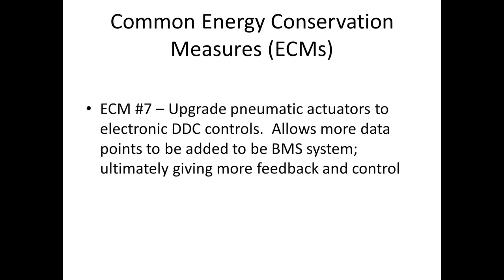A lot of times upgrading pneumatic actuators to electronic DDC controls. This isn't necessarily more inherent, just upgrading technology, but with a lot more electronic controls, we can be a lot more precise and have precise measurements that are fed back into a BMS system, and a lot more data available to review and control logic and make adjustments relatively smoothly, which is the unlikely scenario with pneumatic actuators.